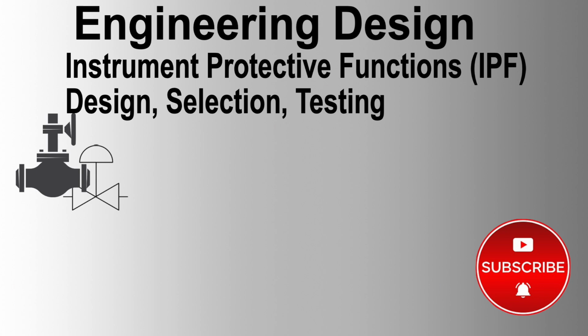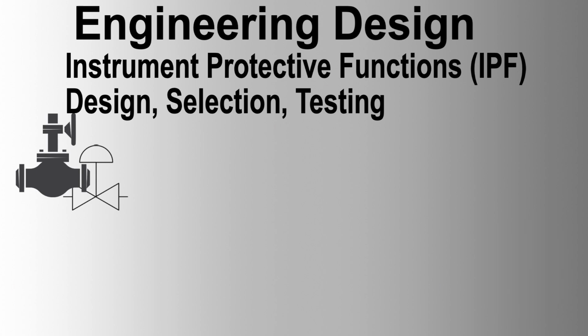The operator should be continuously informed of the system status through IPS system and utility alarms transmitted to the DCS. These alarms are supplier-specific and should be included in the scope. At a minimum, a common cabinet utility alarm and a common system alarm should be transmitted to the DCS for the operator's attention. For IPS system and utility alarms, additional diagnostic information may be transmitted from the IPS to the DCS as indicated in the requisition. A hardwired alarm should be provided for total IPS failure. The supplier should provide a list of parameters that may cause a trip if not properly set.